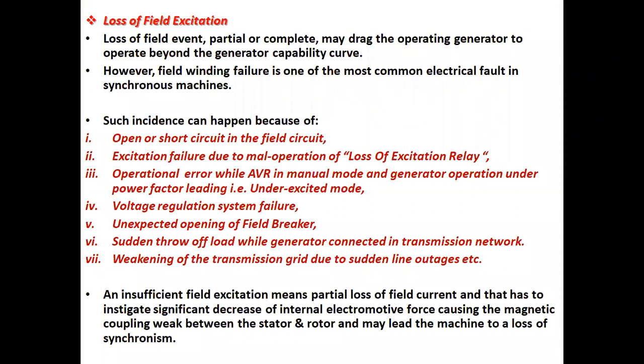Let's start with loss of field excitation. A loss of field event, partial or complete, may drag the operating generator to operate beyond the generator capability curve. Field winding failure is one of the most common electrical faults in synchronous machines. Such incidents can happen because of: one, open or short circuit in the field circuit; number two, excitation failure due to mal-operation of loss of excitation relay.